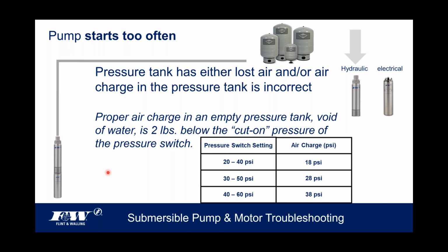So there would be occasions where we either have to add air or remove air, depending on these pressure switch settings over here. You have a 30-50 switch, very popular with submersible pumps. That tank is probably going to ship out with a 28-pound air charge in it. That's where it should be. If you get out on the job and you're going to run that up to a 40-60 switch, you want to put air in that tank, right? You're going to want to add another 10 pounds of air in that tank. Again, this air charge is critical to how a pump cycles, all right?